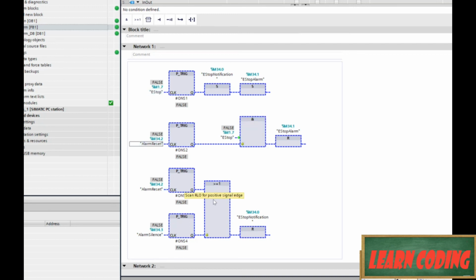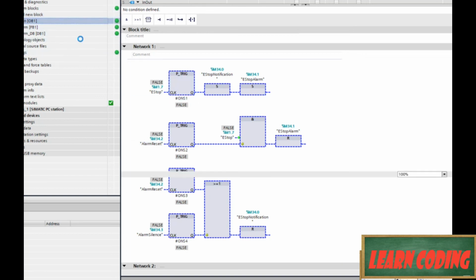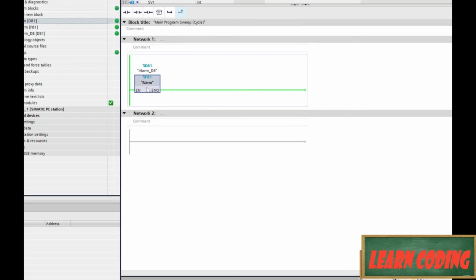And we can set up an alarm like this, and we can make it something general. So like for an analog alarm, we can bring in a high set point, a low set point, a high high, a low low, and a value. And we can just recycle a generic version of this over and over again. And, look what we get whenever we create that. We just get this nice little alarm control that we can just drop into our program. And as long as this is energized, that's off in the background doing all the heavy lifting.